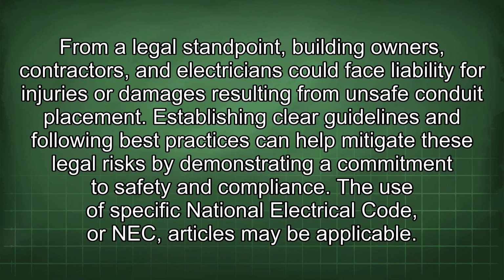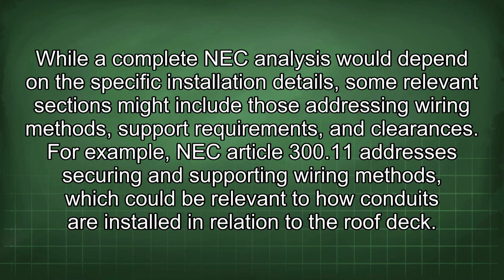From a legal standpoint, building owners, contractors, and electricians could face liability for injuries or damages resulting from unsafe conduit placement. Establishing clear guidelines and following best practices can help mitigate these legal risks by demonstrating a commitment to safety and compliance. The use of specific National Electrical Code, or NEC, articles may be applicable. While a complete NEC analysis would depend on the specific installation details, some relevant sections might include those addressing wiring methods, support requirements, and clearances. For example, NEC Article 300.11 addresses securing and supporting wiring methods, which could be relevant to how conduits are installed in relation to the roof deck.